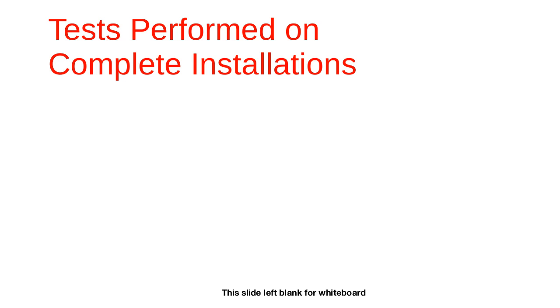These are the tests, the inspection that you'll be carrying out. So we are going to have the inspections. Yeah? So the first inspection under visual inspection requirement is the erection method. Which methods have been used in this installation? And this one should be carried out at the installed stage. So the erection methods should conform to the IEE standards as we've stated above.